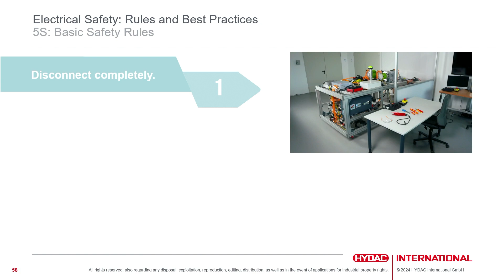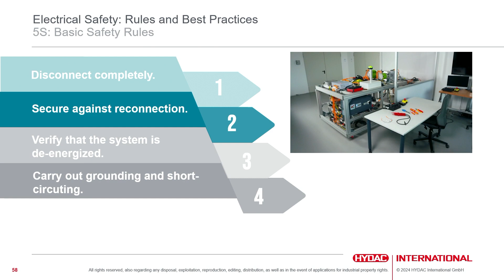When you work with an electric system, the first thing is to disconnect completely. The second is to secure against unwanted, undesired reconnection. The third is to verify that the system is de-energized - not only switch off, but really check that there's no unexpected voltage in the system anymore. Then there are two more points: carry out grounding and short circuiting, I'll come to that in a minute, and provide protection against adjacent live parts with covers or barriers.